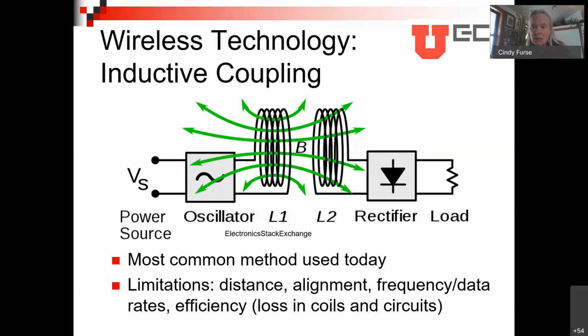This can also be used for rudimentary data transmission. So it's not high data rates. Certainly, this isn't a video link. It's very low rate data transmission, and there are some pretty significant challenges. Distance is the biggest. Inductive coupling, you need to have the two coils very close. Rule of thumb is that you want to have the coils close enough that they're within the diameter of the coil, so very, very close. So you can't get a lot of wireless transmission. It's only wireless through the skin.